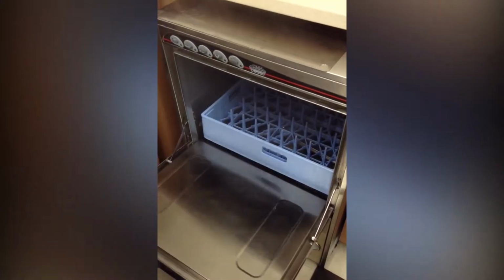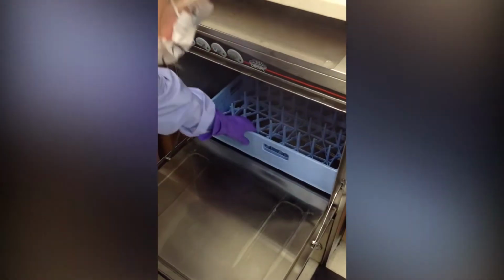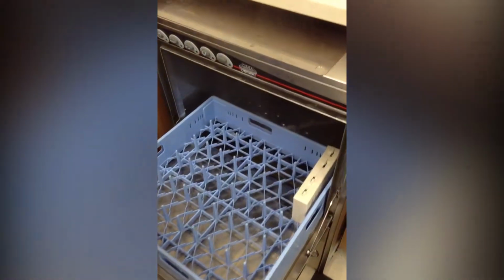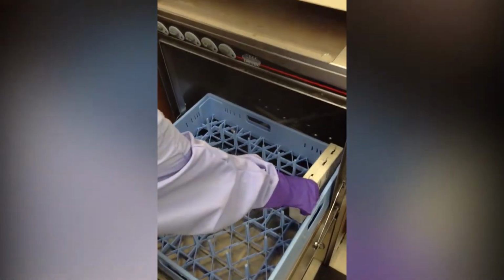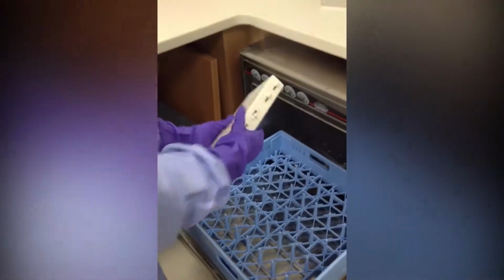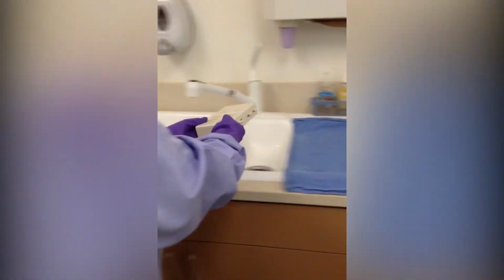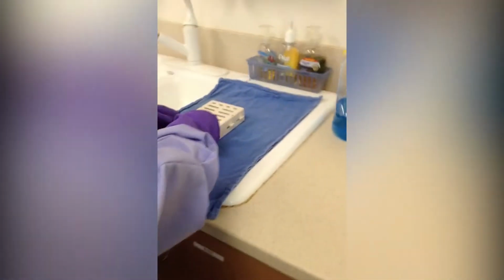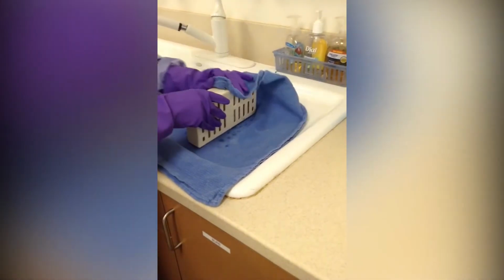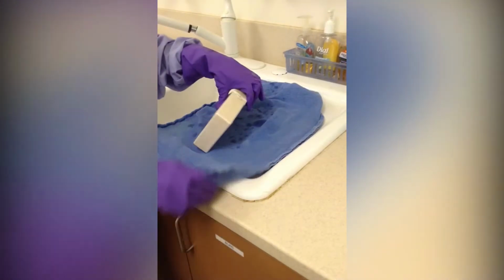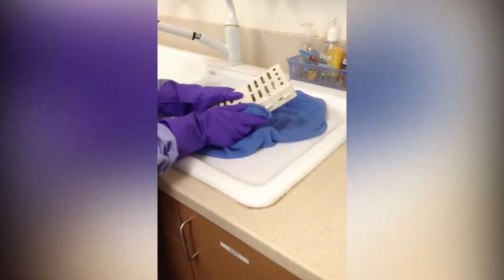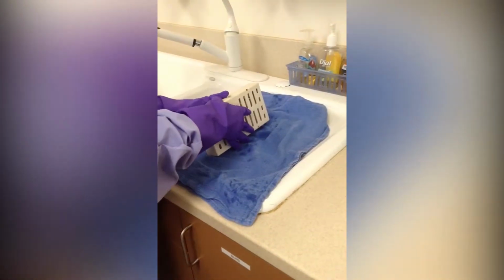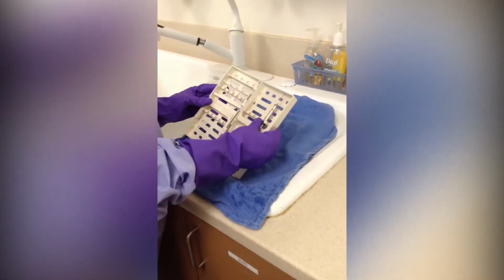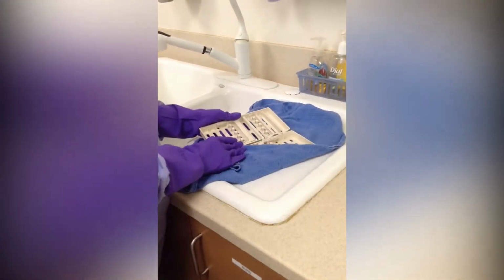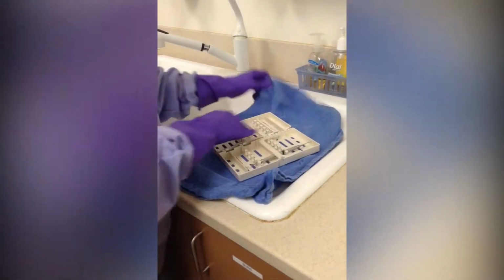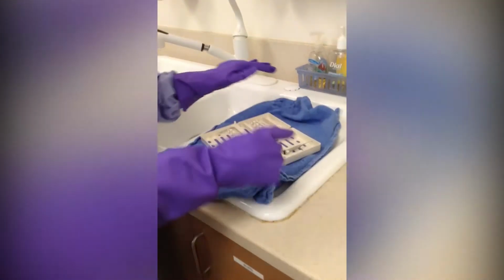Now once you hear the washer finishing, wait for it to stop completely and open the door. Remove the cassette. Put it on the blue towel, dry the instrument, and inspect for any broken pieces. Dry the cassette. This is the drying step in instrument processing.